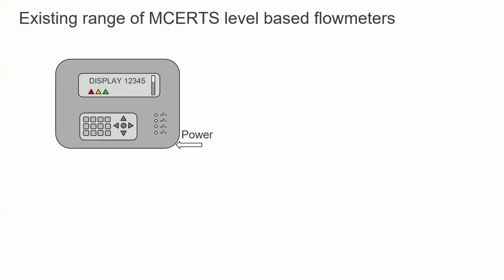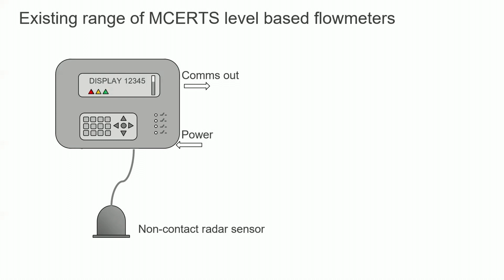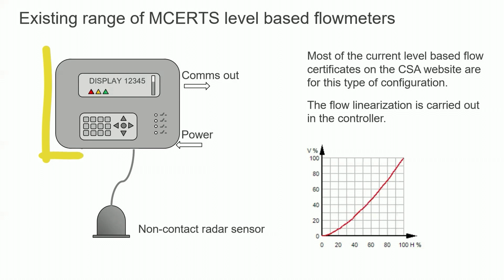A non-contact sensor, such as an ultrasonic transducer, can be connected to that. But the ultrasonics may, in fact, need an additional temperature sensor to improve the accuracy class, and maybe the addition of a sunshade or two. However, there are smart level transmitters, including radars, that can connect to controllers such as this. However, the non-contact radar will not need temperature compensation. So the non-contact radar and the controllers themselves will have a comms output, so there could be data logging in various different formats. But if we look at it, most of the current level-based flow certificates on the CSA website are of this basic configuration. So the flow linearization is carried out inside the controller.